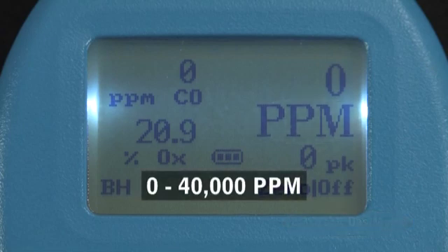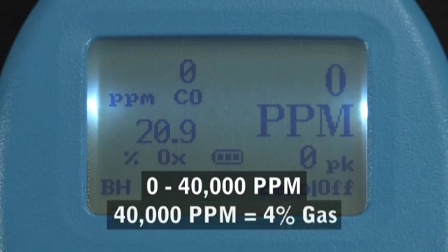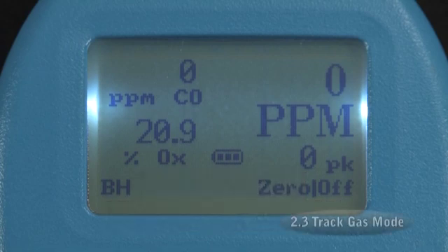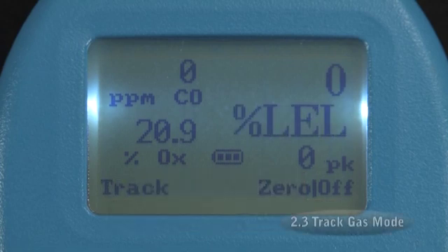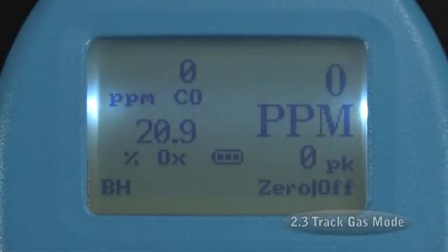The Explorer reads in 20 ppm increments, from 0 to 40,000, which is 4% gas. At 4% gas, the Explorer automatically rolls back into the monitor mode. In the lower right of the track gas screen, you will see the same two options as in the monitor mode, Zero and off. In the lower left of the screen, you will see BH, indicating that you can enter the bar hole mode by pressing the left button.